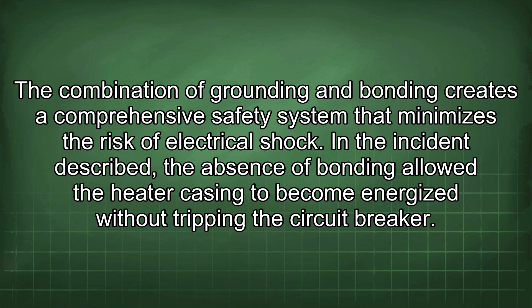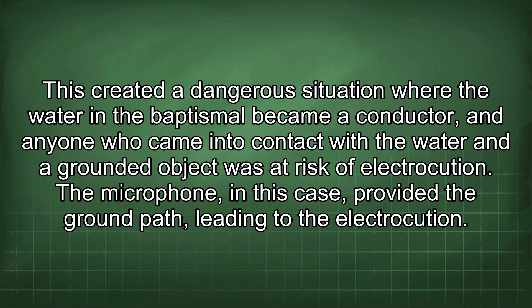In the incident described, the absence of bonding allowed the heater casing to become energized without tripping the circuit breaker. This created a dangerous situation where the water in the baptismal became a conductor, and anyone who came into contact with the water and a grounded object was at risk of electrocution. The microphone, in this case, provided the ground path, leading to the electrocution. The fact that another person experienced a shock when they grabbed the microphone further emphasizes the severity of the situation. A properly installed GFCI would have detected the ground fault and tripped the circuit, preventing the electrocution.